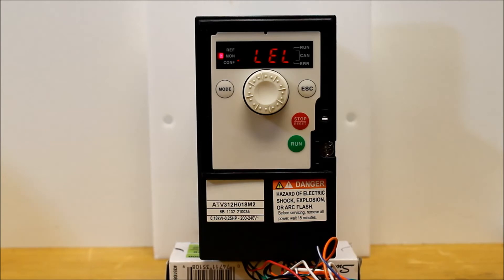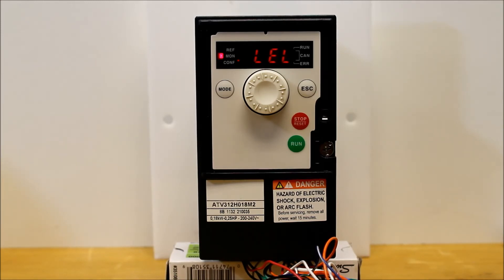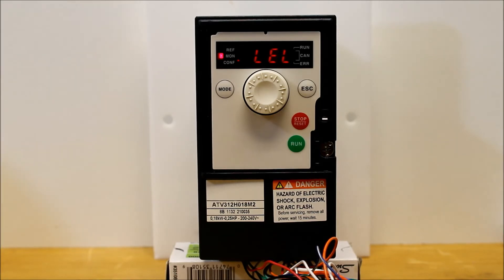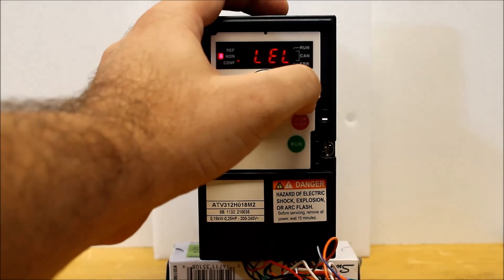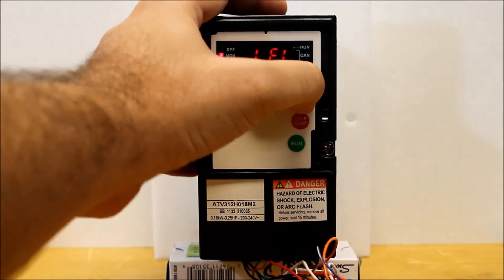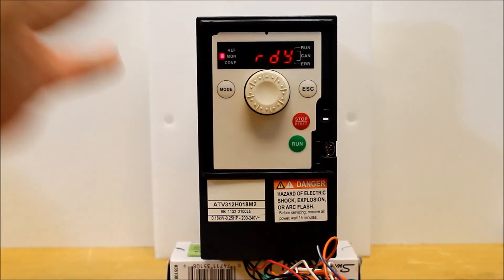You don't have to wait until the drive is powered up to toggle your run command, which might be important for some kind of safety issues depending on how your setup is. But this is important for level control. It's important for when you're doing automatic restart and the like. So now that we've done that, it's already set up for two-wire. And I already have a speed reference of some kind coming into this drive. So we can escape back out.